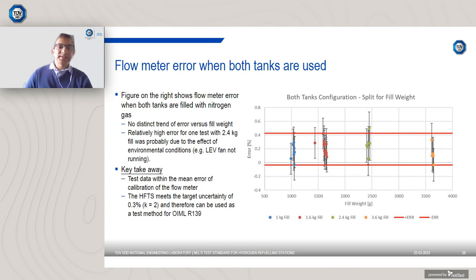So what we've done here is only consider if both tanks were filled with nitrogen gas. And what you can see essentially is that there is no distinct trend of error versus the amount of gas that you have filled. Which is a good thing in one sense, because essentially you don't need to apply any correction or any correction curve as such.